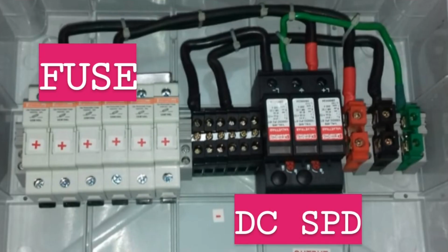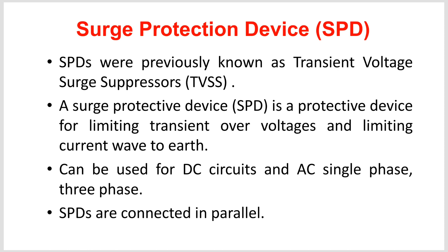Friends, SPDs can be of both types, AC SPD and DC SPD. You can see both types of SPD in solar power plant installations. In ACDB you use AC SPD, and in DCDB or array junction box you use DC SPD. But the purpose and working of both SPDs is the same, which is to limit the overvoltage transient surge.